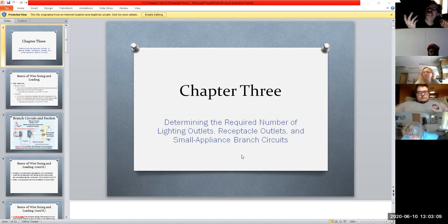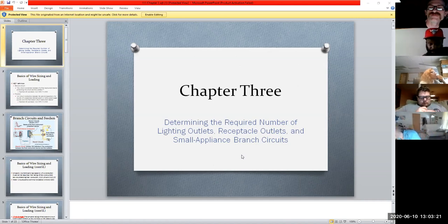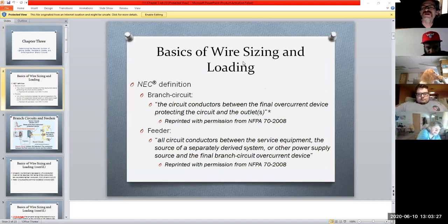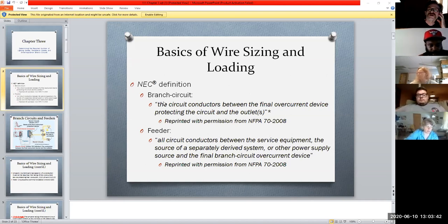So with this one breaker, I might be energizing like 3 different luminaires or so many receptacles. But how do we go about doing that? Well, chapter 3 starts to talk about that. How do we figure out wire sizing and the loading, right? Earlier we talked about ampacity, and ampacity is the ability to deliver current. Doesn't mean we're always going to be energized with that amount of current. But when we look at a branch circuit, the circuit conductors, the wire between a final overcurrent device protecting the circuit and the outlet.